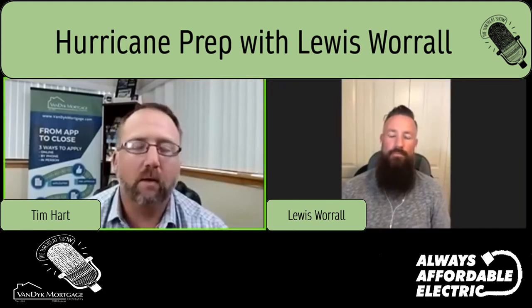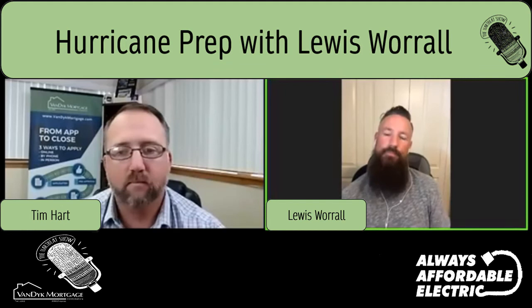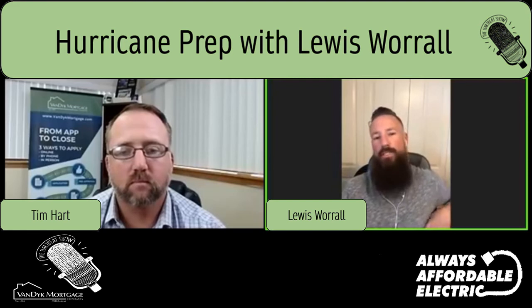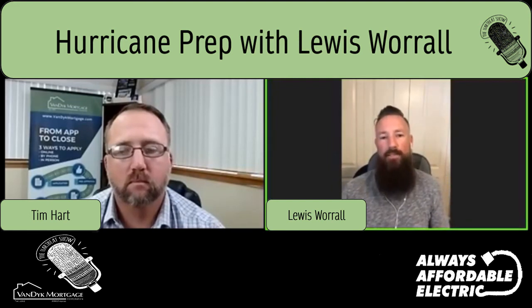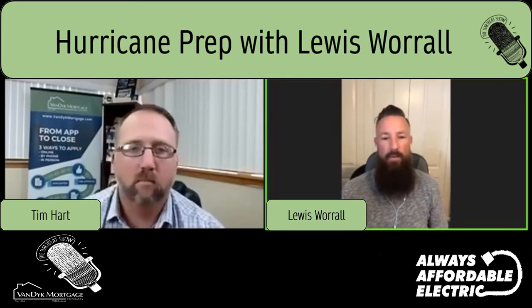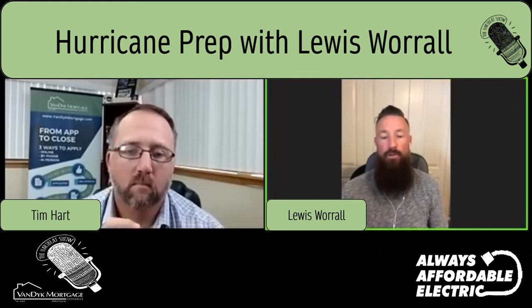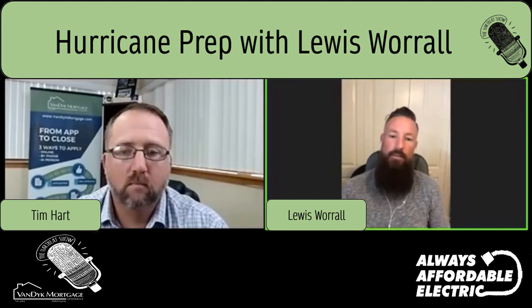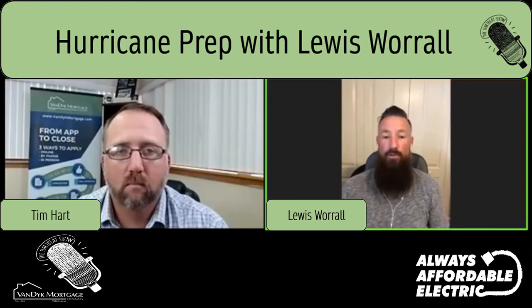Okay. So the other thing we want to talk about is surge protectors for your house. Especially if you're going to do a generator setup. A lot of people use LCEC and FPL, but the problem is that if you have the manual transfer or even the automatic transfer, it disconnects power from the main breaker. At that point, you don't have surge protection anymore, because their surge protection is on the collar of the meter. The surge protection we install is at the panel or in the panel, so it's after the main power coming in. So when you run your generator, you still have surge protection.